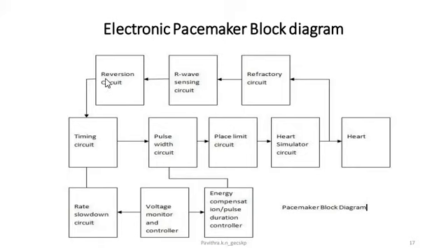And why is it known as reversion circuit or return circuit? Since it allows the return path, since it allows the oscillator to return to its active state. Due to that, we are calling this circuit the reversion circuit. Why? Because it allows the oscillator to revert back to the active state and produce pulses when no R wave input is coming from the R wave sensing circuit.